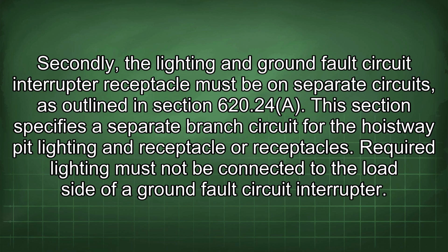Secondly, the lighting and ground fault circuit interrupter receptacle must be on separate circuits, as outlined in Section 620.24a. This section specifies a separate branch circuit for the hoistway pit lighting and receptacle or receptacles. Required lighting must not be connected to the load side of a ground fault circuit interrupter.